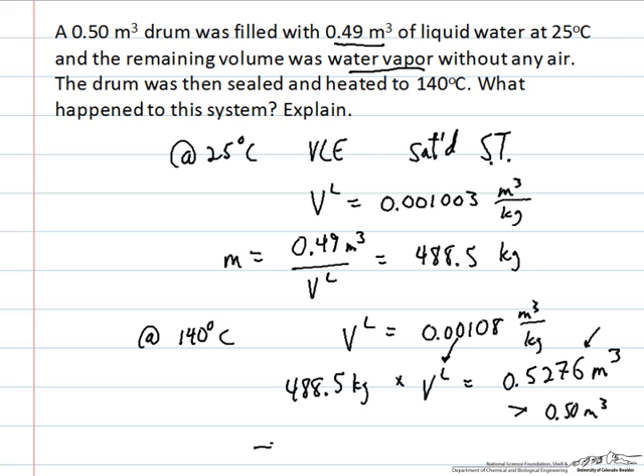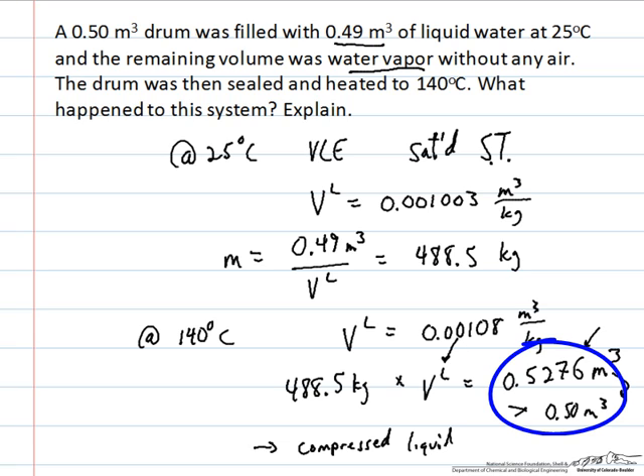Therefore, what forms in this system is a compressed liquid — a liquid compressed beyond its saturated state, at higher pressure than the saturated liquid. Since liquids are largely incompressible, we're looking at roughly a 4% required compression from the saturated liquid to the compressed state, which demands a very large pressure. If the drum is not rated to a sufficiently high pressure, the tank would potentially rupture.